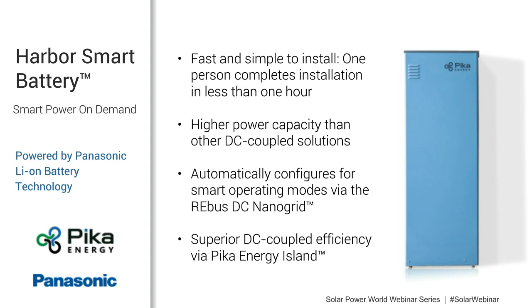It's a suite of products that are all designed to acknowledge each other, configure to each other, and follow operational modes. They're very simple for the user to select. And with DC-coupled efficiency, your DC efficiency on your system is going to be north of 95% from your PV to your battery and back out of the battery. And so that really makes a huge difference in the lifetime return for these systems when you're using them for financial gains. So if you're in a market where a battery helps you to manage your electrical costs, that higher round-trip efficiency is going to be really important over the lifetime of the system versus some of the other systems that are on the market.